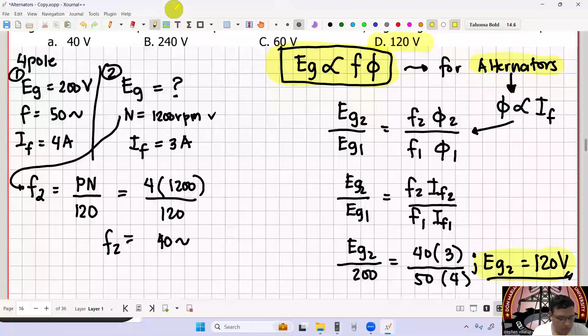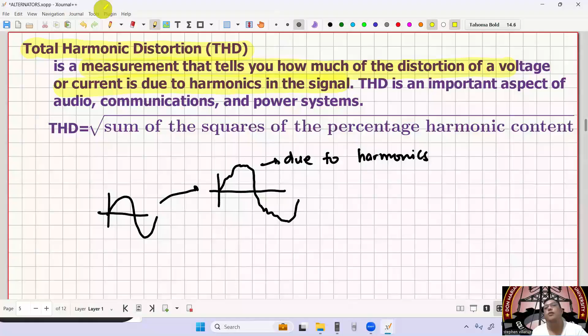But before that, let's discuss total harmonic distortion. Take note, for alternators, the voltage that is supposed to be generated as sinusoidal does not end up perfect. It develops spikes eventually, and this is due to harmonics. So the THD or total harmonic distortion is a measurement that tells you how much of the distortion of a voltage or current is due to harmonics on the signal.